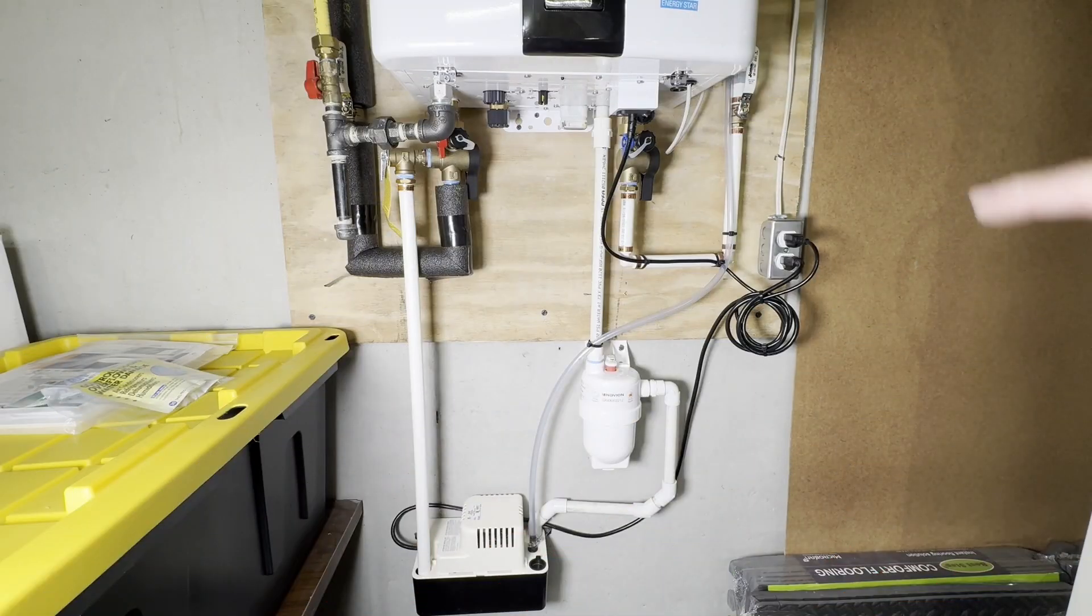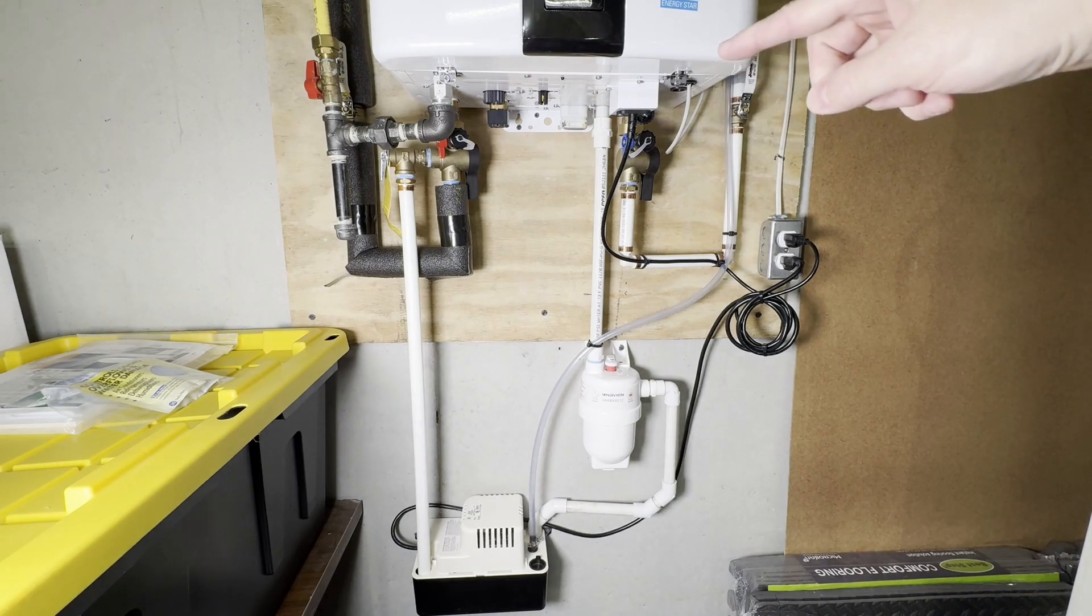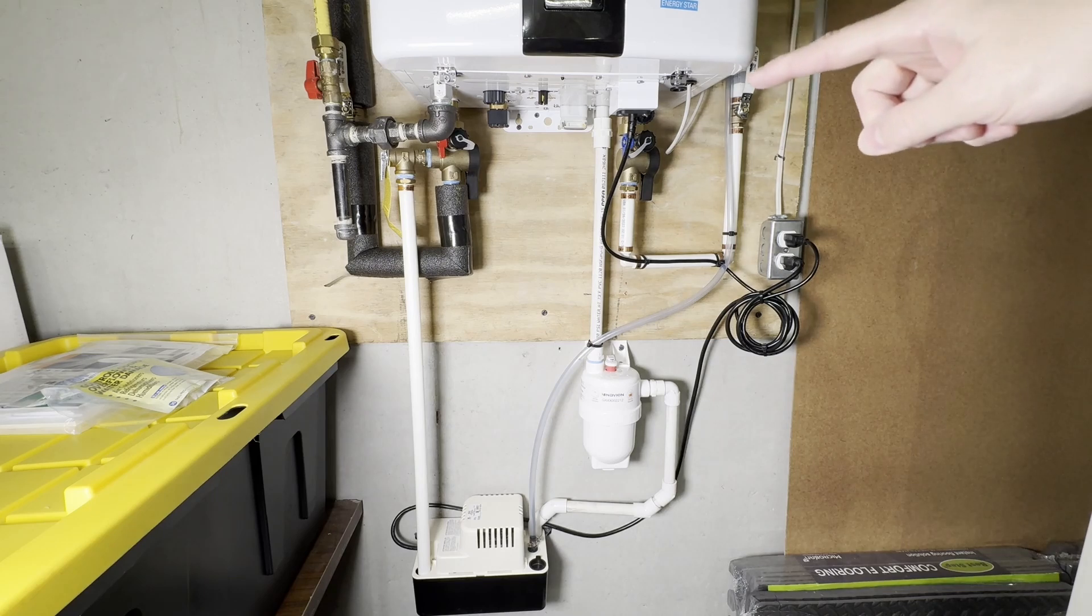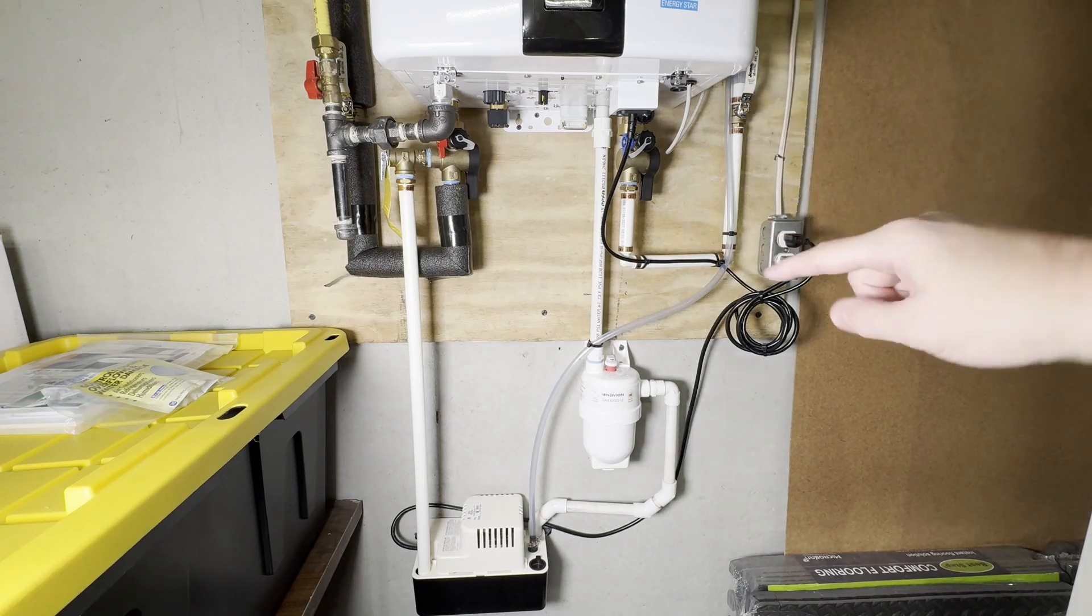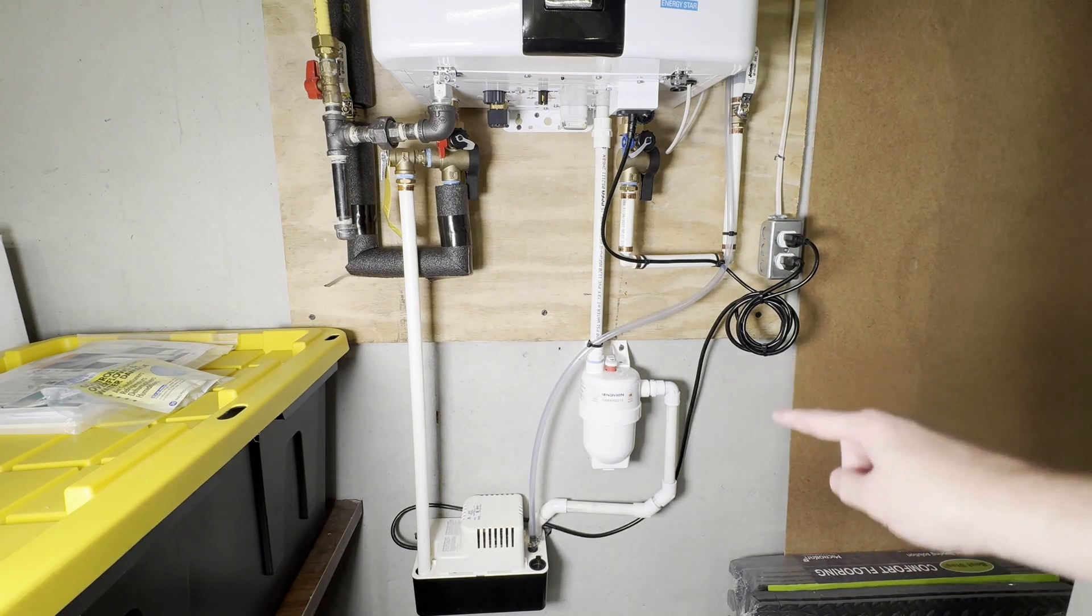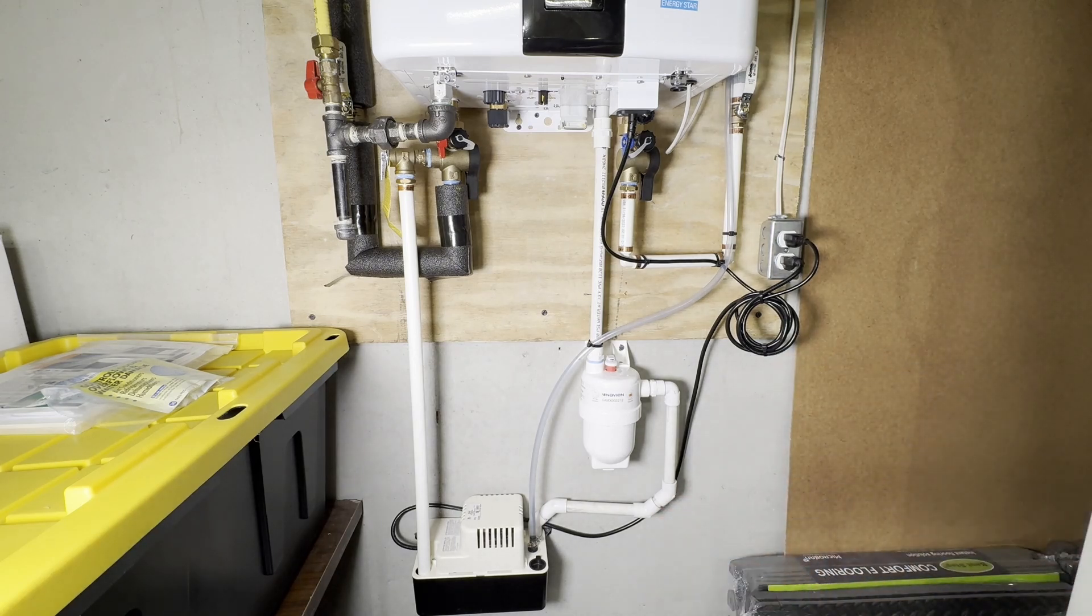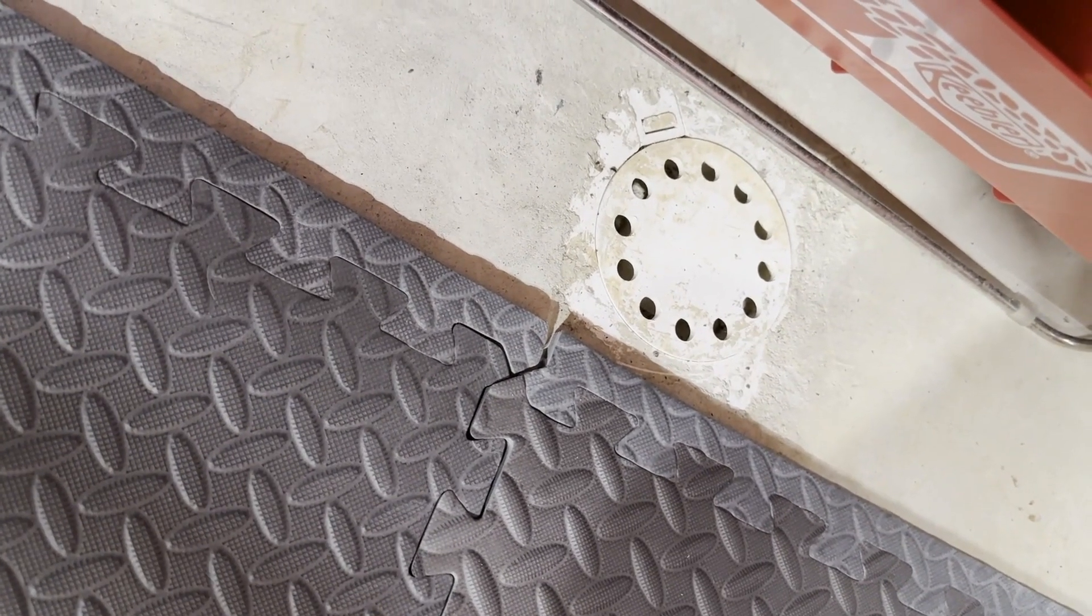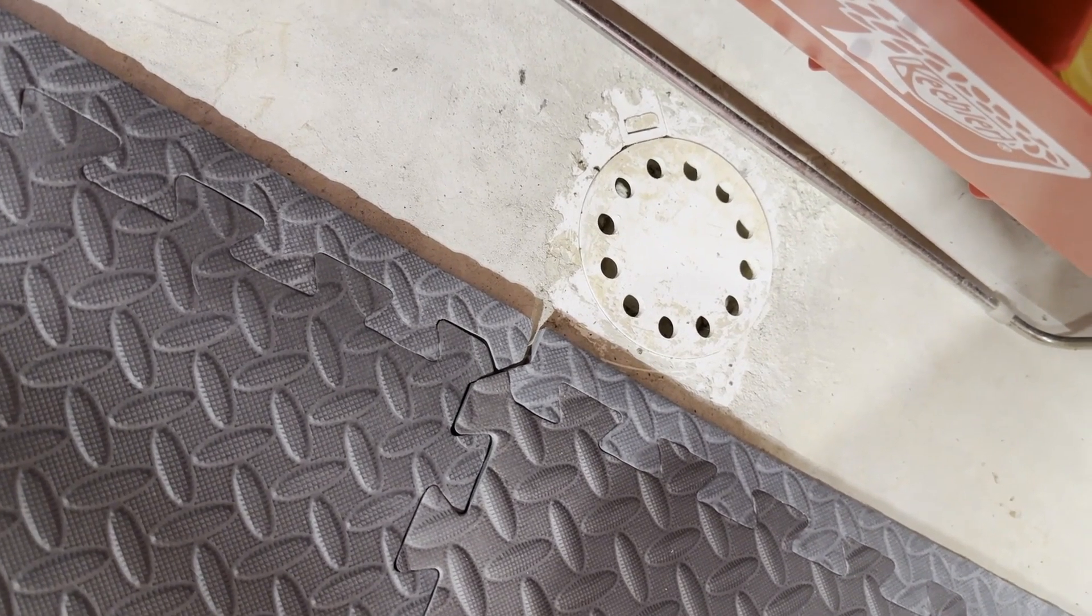The concept is the tankless water heater is very efficient and creates very acidic condensate. When it comes down into this acid neutralizer, it's supposed to neutralize the acidity in the water before sending it out to the sewer, because it could damage metal pipes. I have PVC for my sewer pipe, but this may also be code in my area or your area, which is why they installed it. Your unit may be dumping directly into a floor drain without an acid neutralizer.